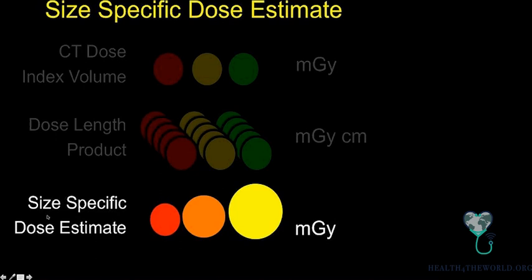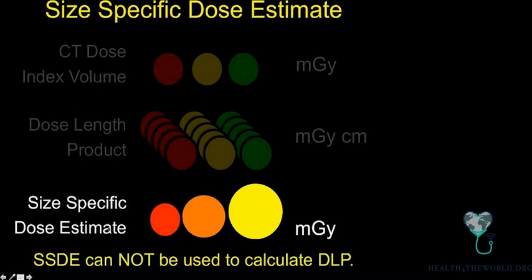There is also something called the Size-Specific Dose Estimate (SSDE), referenced in some papers. Like CTDI volume, it reflects average slice dose, but it takes into account how big the patient is — adjusting for a larger or smaller patient. It's only in milligray, and you can't use SSDE to calculate DLP. It's a dead-end number used in literature, not something on your standard report because current scanners don't account for patient size automatically.